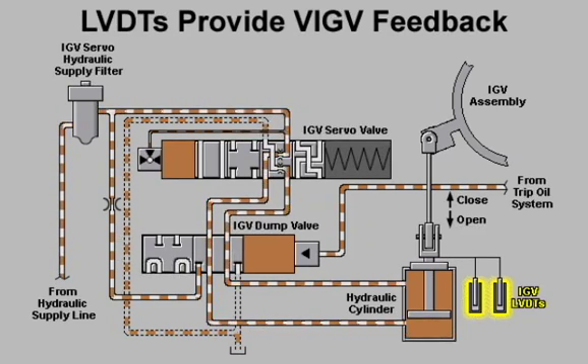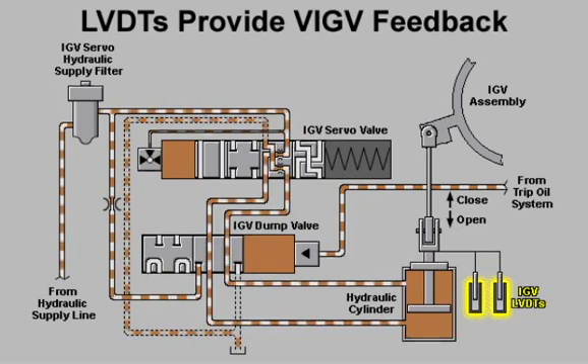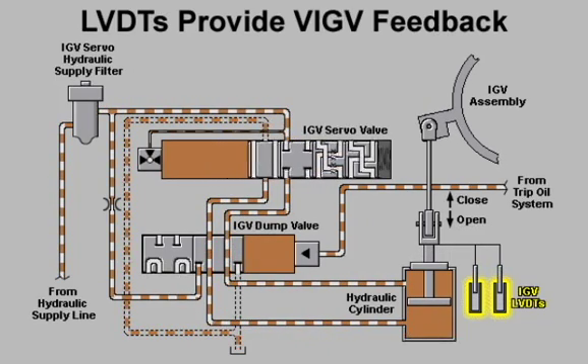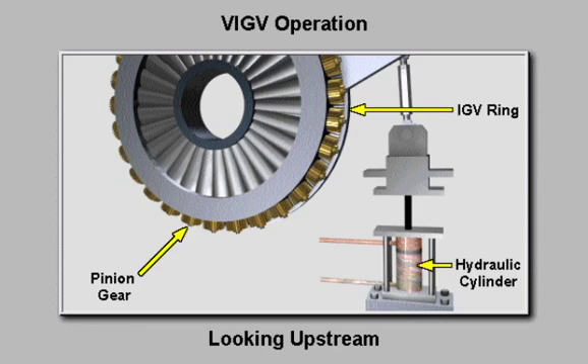When the commanded IGV angle and the actual IGV angle are the same, the control system resets the IGV servo valve to its null position. Actuation of the inlet guide vane ring by the hydraulic cylinder pivots the guide vanes about their mounts and increases or decreases the effective inlet area of the compressor.